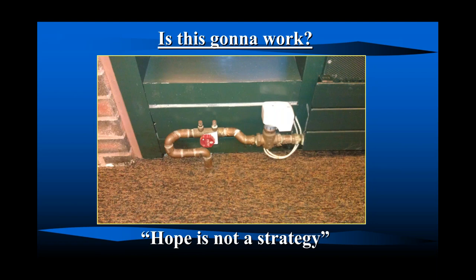What could possibly happen? Well, what is this terminal unit right here? That's a panel radiator. And if I was designing a panel radiator system, it'd be really low temperature, because this thing's about ankle high right there. And if this is not balanced, to do it right, you have to touch that red disc and probably 100 other red discs to make it work perfectly. If that's what you do, that's great. But if it doesn't, and if this zone doesn't get the temperature, it doesn't keep temperature, instead of touching all those red discs, you're probably going to turn up the temperature supplied to this device. And that's where it gets kind of dangerous, because that's ankle high.